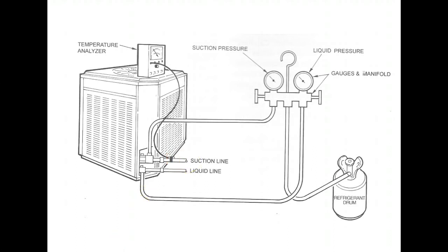If you are measuring subcooling, you'll do the gauge setup exactly the same way except you'll take this temperature probe over here and you're going to move it onto the liquid line and make sure that it's securely fastened to the liquid line. If you're using a clamp-on type thermocouple or temperature probe, that is usually sufficient. But if you have just an open type probe, you're going to want to insulate this temperature probe from the outside air. So wrap a piece of insulation around there so that it's only measuring the suction line or the liquid line temperatures.